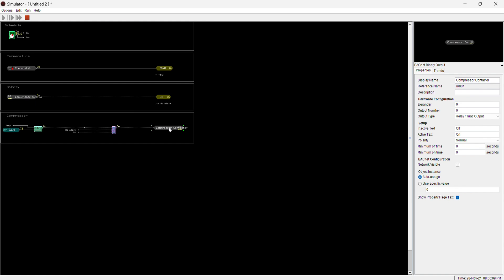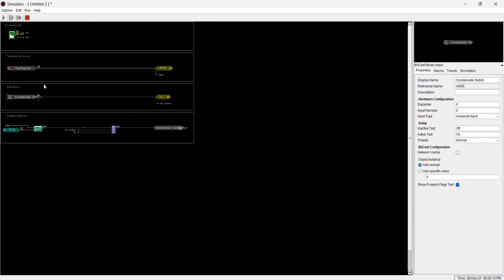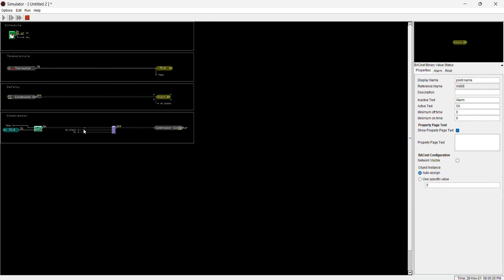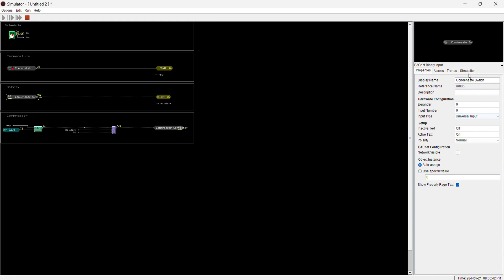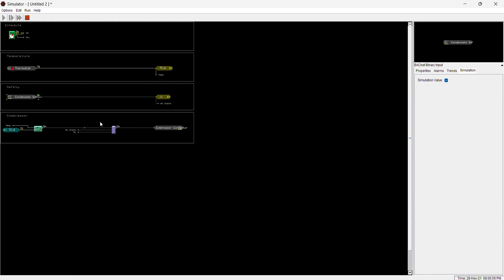In this safety, I can have a lot of safeties — more AND blocks, more safeties. If any of them trip, for example if this one trips and I put it OFF, you see it shows 'Alarm' and it won't send 24 volts. That's the point I'm driving: if a safety is tripped it will not send 24 volts to whatever you're trying to turn on; it needs to be in the closed position. Some programmers program this the opposite way — if it's OFF that's a YES — but they have to add a NOT block. I like to keep it simple: if it's good, it sends an ON signal, all inputs are ON, and that sends the ON signal.